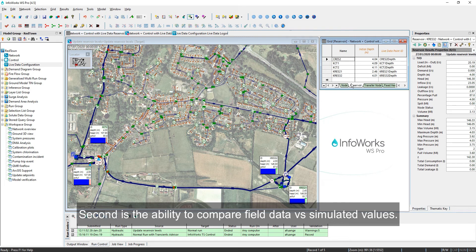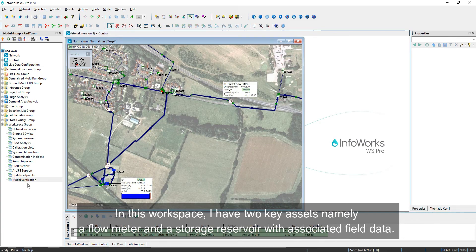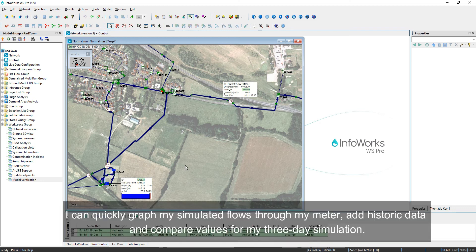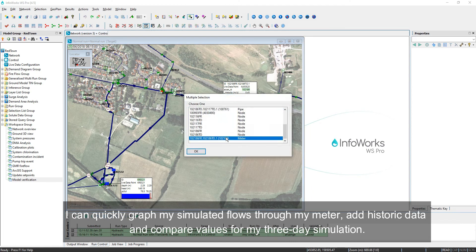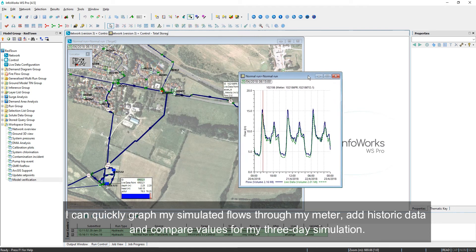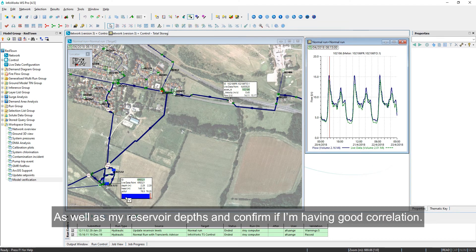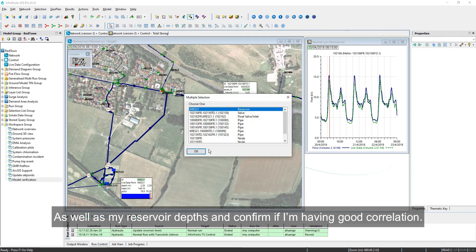Second is the ability to compare observed versus simulated values. In this workspace, I have two key assets — namely a flow meter and a storage reservoir with associated field data. I can quickly graph my simulated flows through my meter, add some historic data, and compare values for my 3-day simulation, as well as my reservoir depths, and confirm if I'm having good correlation.